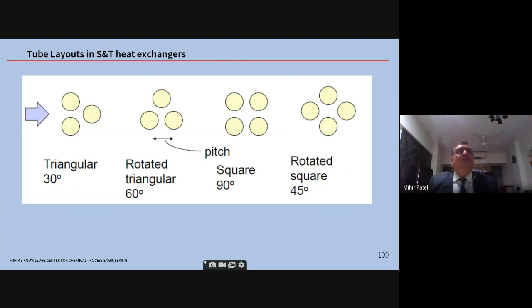And tube layouts. Now, as one can see, you have the different tube layouts. These are very important from a process engineer's perspective. He is the best person who knows the type of fluid. So triangle 30 degree angle, this will give you the smallest shell ID. More tubes can be packed, but cleanability is an issue. Okay. Rotated triangle 60 degrees optimization from pressure drop perspective. The 90 degree square and the rotated square are the best for cleanability services.